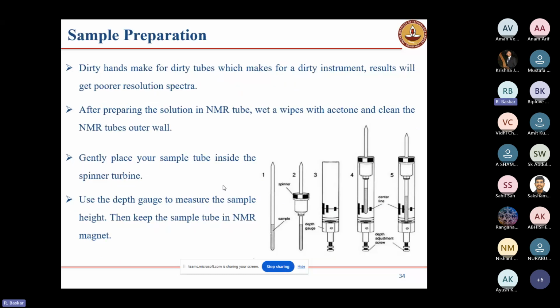When we are preparing the NMR sample, our hands should be clean, because dirty hands make dirty NMR tubes, and that will make the instrument dirty and give a poorer resolution NMR spectrum. After preparing the solution, wipe the NMR tube with acetone on tissue paper and clean the NMR tube. Gently place the NMR tube inside the spinner and we have to measure with the measuring gauge for the proper height.